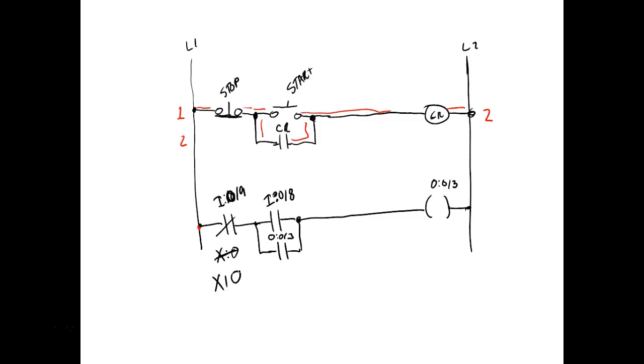But what would happen, that's my stop circuit. If a wire opens, it's going to open, right? You understand? It's going to open. Well, I'm using a normally closed, examine if open, so it's true, right? You understand that? And I couldn't stop my circuit. So if a wire opens, you could go over and you could beat on that push button all day long, and it's not going to do it. It's not going to stop.